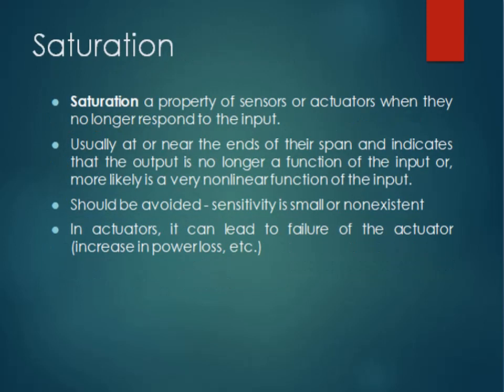Okay. Now we'll talk about saturation. Basically saturation is a property of sensors or actuators when they no longer respond to the input, usually at or near the end of their span. It indicates that the output is no longer a function of the input, or more likely is a very nonlinear function of the input, and it should be avoided because sensitivity is small or non-existent. In the case of an actuator, it can lead to failure of the actuator, like increasing power loss, etc.